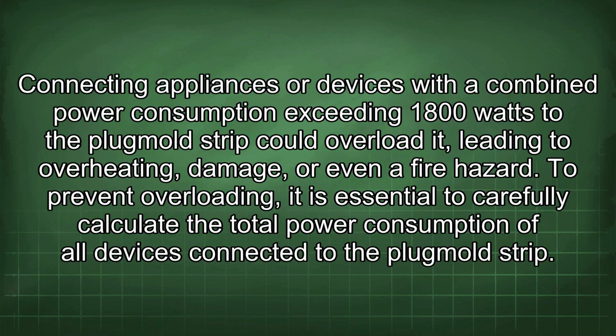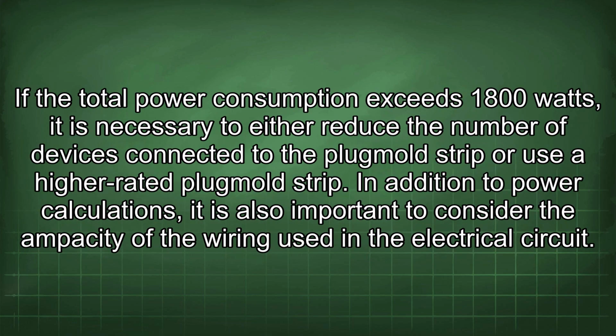Connecting appliances or devices with a combined power consumption exceeding 1800 watts to the Plugmold strip could overload it, leading to overheating, damage, or even a fire hazard. To prevent overloading, it is essential to carefully calculate the total power consumption of all devices connected to the Plugmold strip. If the total power consumption exceeds 1800 watts, it is necessary to either reduce the number of devices connected to the Plugmold strip or use a higher rated Plugmold strip.